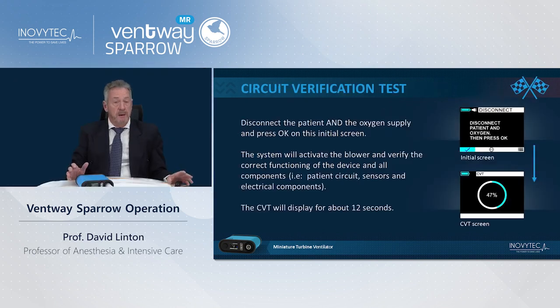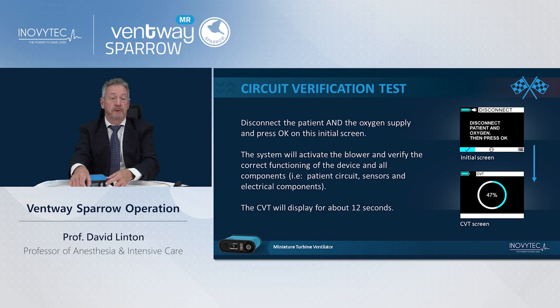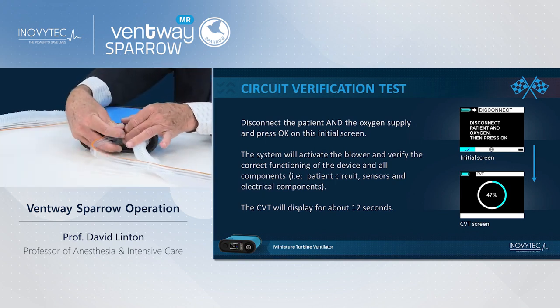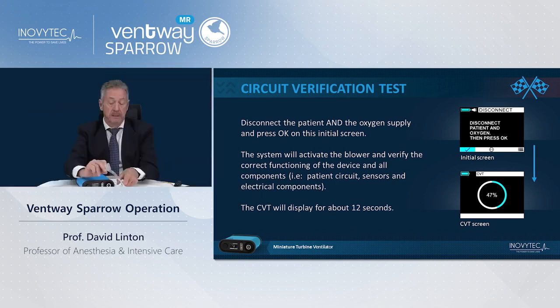The first thing that will come up after the logo is a circuit verification test. To do the circuit verification test, you have to have the ventilator circuit plugged into the right place, and it can only go in one way. There's a flat end and a round end. It can only go in one way, okay?